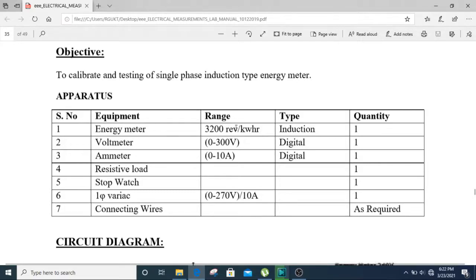The energy meter has a meter constant of 3200 revolutions per kilowatt hour. This is the meter constant of this energy meter. The type of this energy meter is induction type. Coming to the voltmeter, the range of the voltmeter is 0 to 300. Here in this experiment we use a 0 to 300 volts range voltmeter. Next we use an ammeter. It has a range of 0 to 10 amps.